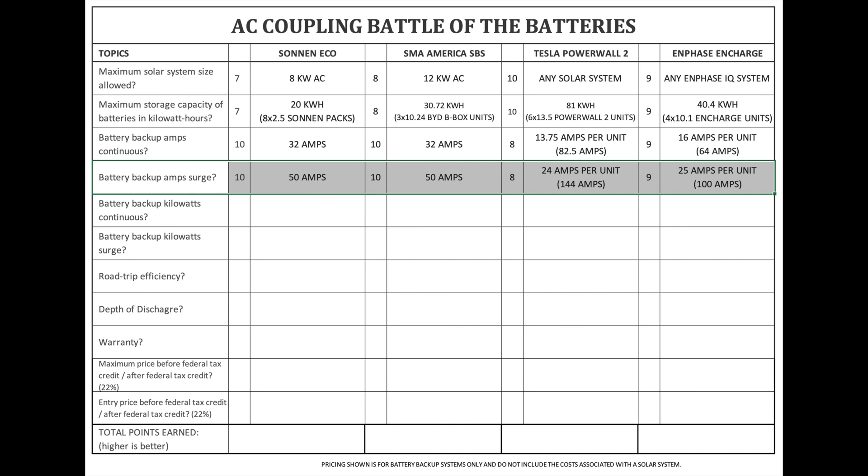Battery backup amps surge. The surge is equally important to the continuous amps because some devices, like a refrigerator, will have a spike in amps which need that surge to start the compressor. But once it's running, the amps go down to a steady flow. The surge is usually less than 30 seconds. The Sonnen Eco is 50 amps. SMA America's SBS is 50 amps. Tesla Powerwall 2 is 24 amps per Powerwall — if you connect six of them together, you can have up to 144 amps of surge capability. Enphase Encharge is 25 amps per Encharge 10, up to four units connected together for 100 amp surge.